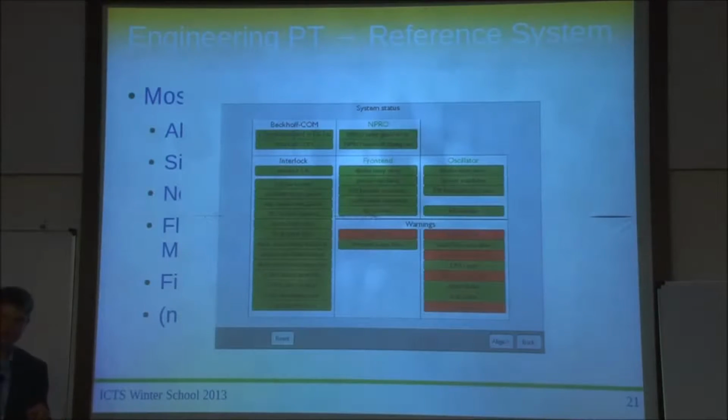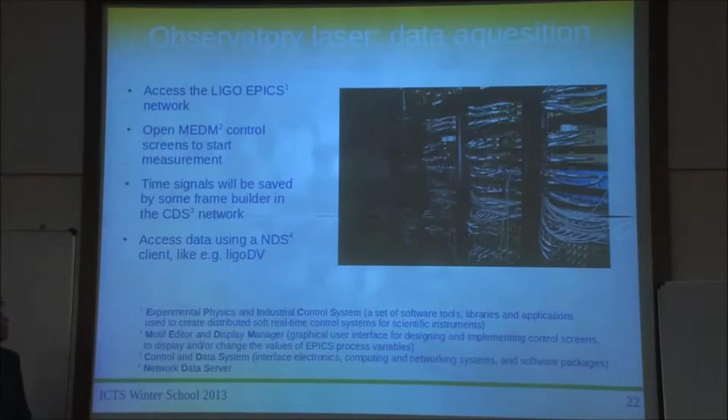So the last message that you see when you come into the lab was always interlock triggered, but you don't know why. That's why we came up with this little screen, which has these green and red boxes, also a couple of warnings. In this case the system would run because those are only warnings, like somebody opened the lid of the oscillator, somebody opened the lid of the front end, and so on. Those are things which just let you be aware of other things.